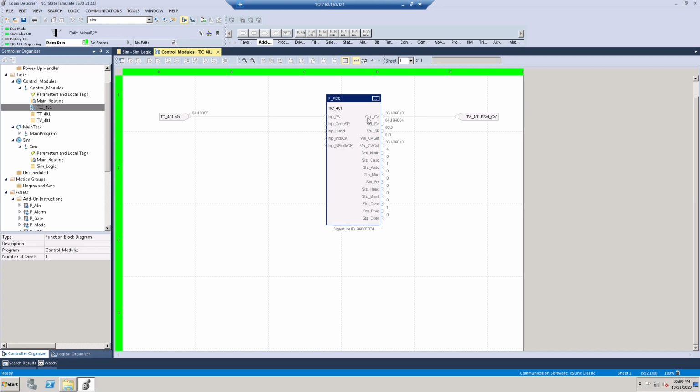There are two big factors at play that create this offset. Our sim logic is imperfect. It doesn't represent how the amount of steam actually impacts the temperature. And second, we would definitely have to play around with our proportional, integral, and derivative gains.